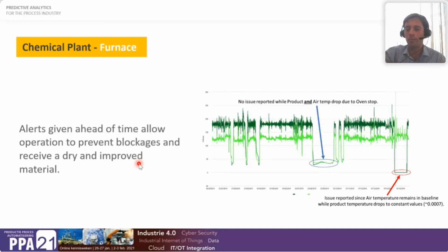Here they were lucky that we found it on time because they just changed the sensor. It cost them $1,000 to change the sensor. But if they kept trying to dry the material in this chemical plant with no idea of the real temperature of the material coming out of the furnace, and it starts to get too wet, eventually you'll get a blockage. When this furnace chokes, it cannot work and they're losing production - this is the most important furnace on site. So we gave them a heads up ahead of time, preventing a blockage and the loss of product.